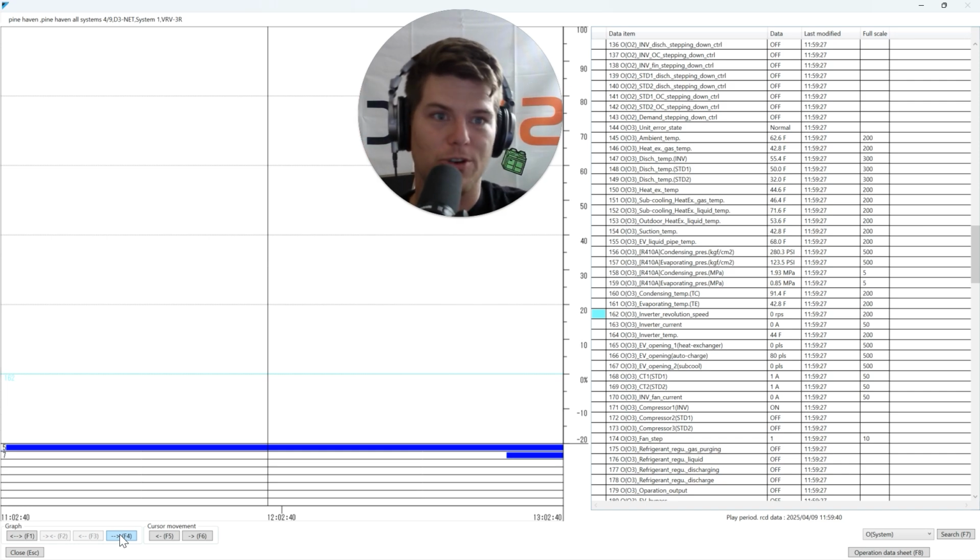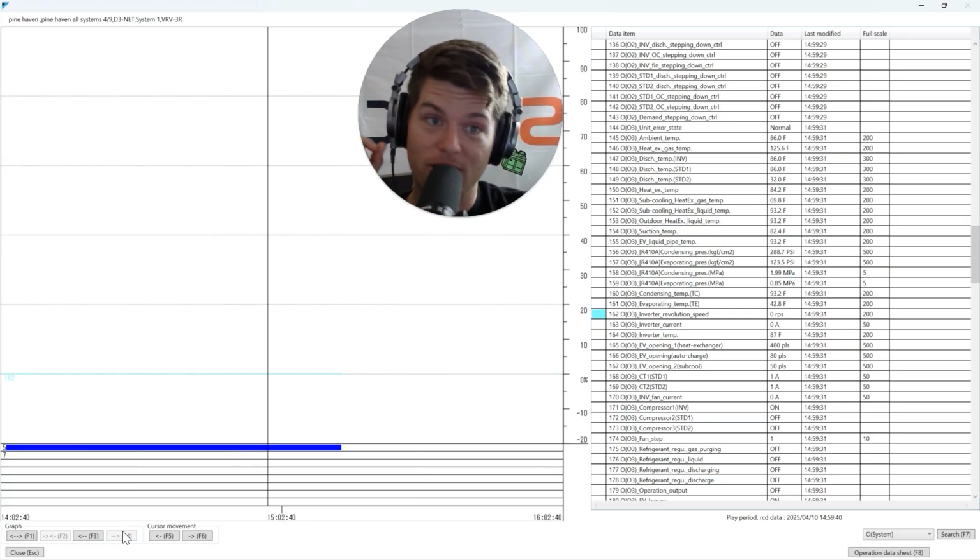What is it supposed to do? It's supposed to turn on that third compressor, that third module, to increase the demand on the system. And guess what, buddy? It never did it. And why didn't it do it? Because it's locked out. See, it's one of these things where we take small things like that for granted. If I can go through this entire data set and see that this compressor never comes on, well, buddy, gosh golly, that sub 2 module is completely locked out.